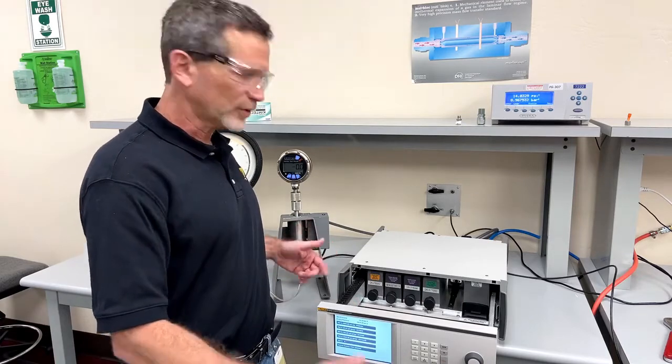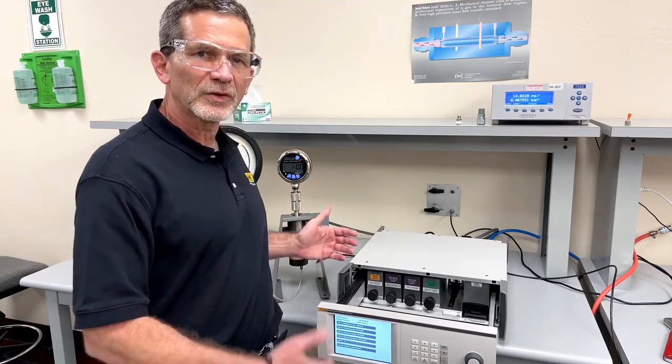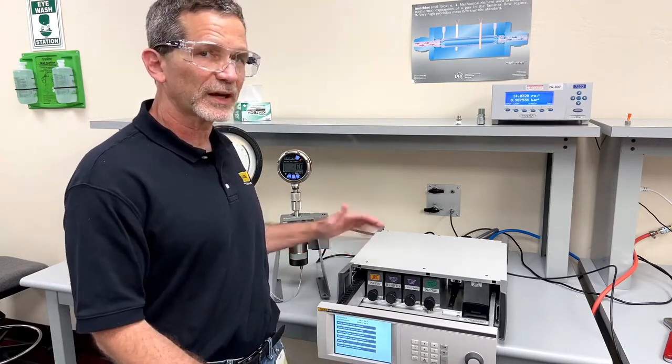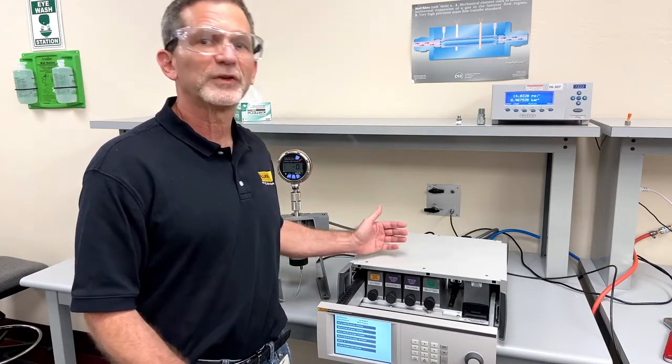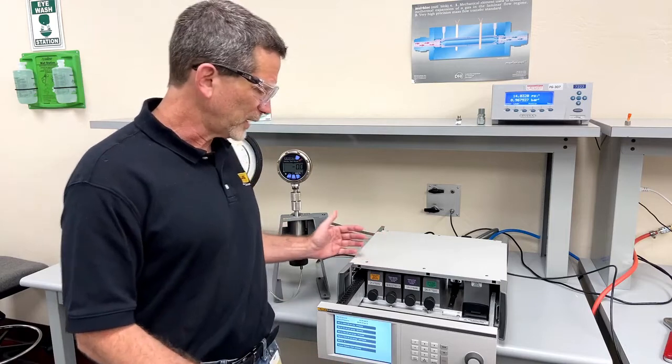All of our pressure controllers have very wide-ranging turndown, so you can just as easily do a 6,000 PSI calibration with the 8270 as you can a 50 PSI calibration without having to make any changes.